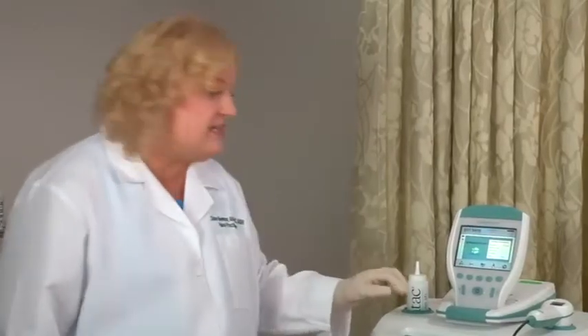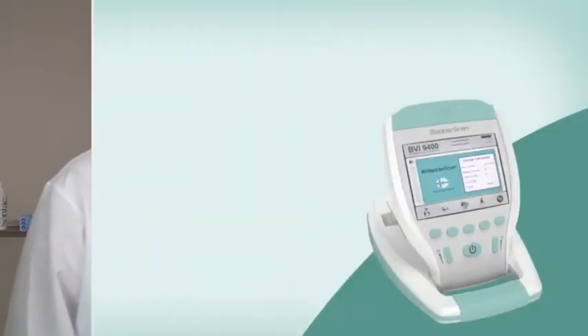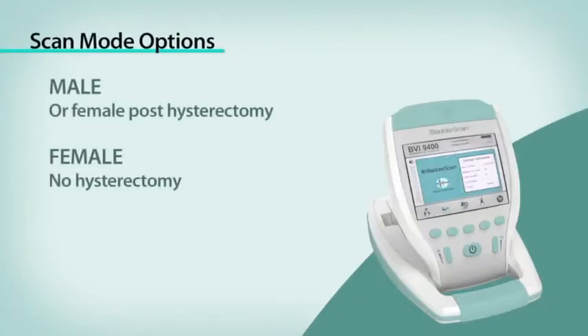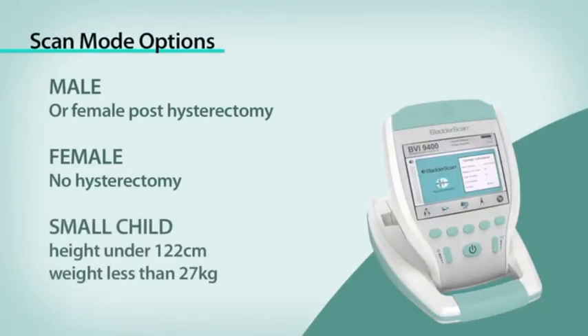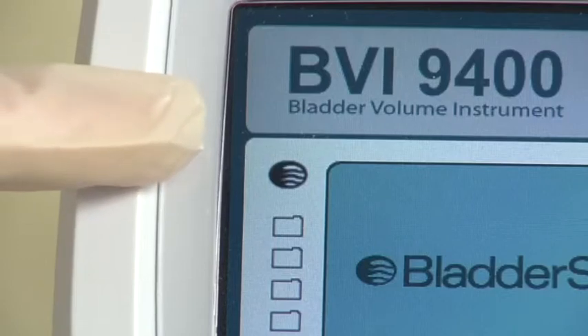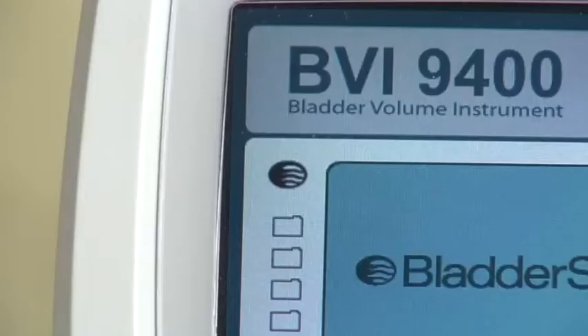Turn on the BladderScan by pressing the on-off button, which is right here. The BladderScan BVI 9400 is designed to scan in 3 specific modes: male patient, female patient, and small child. A female patient who has had a hysterectomy should be scanned in the male mode. This is shown as a bladder icon. To begin, first select the proper exam mode to ensure the accuracy of your scan. Press the mode button repeatedly until the right setting appears. Select to scan a male patient or a female patient who's had a hysterectomy. Select to scan a female patient who has not had a hysterectomy, or select to scan a small child under 48 inches, 122 centimeters tall, and weighing less than 60 pounds or 27 kilograms.